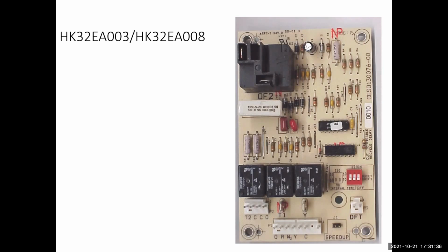relay resistor located on the right side, right here where it tells you, cut disabled, recycle delay. You will cut that. However, once you cut that feature, it cannot easily be replaced or repaired. So really know if you don't want that in your cycle. Also noted, this control is not a direct replacement for the HK32001 that we talked about prior.